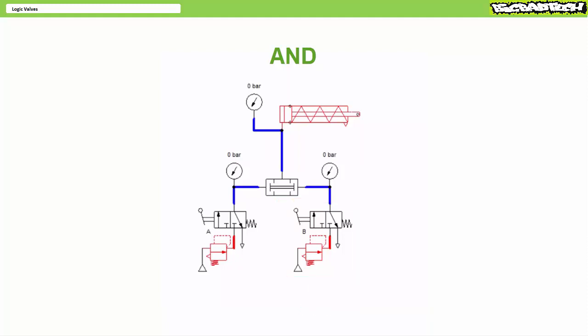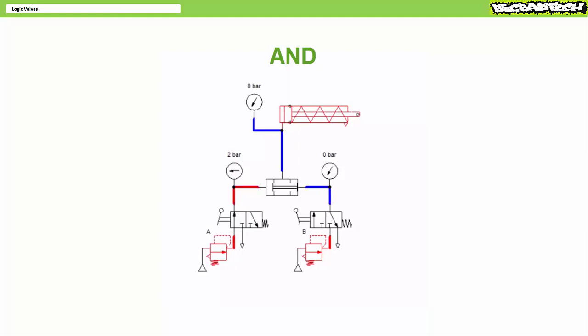Recall an AND valve behaves as follows: there must be a pilot signal at both inputs A and B for there to be an output. Additionally, when both air pilots A and B are present, it selects the lowest of the two pressures. When neither A nor B receive an air pilot signal, the AND valve produces no output. When only A receives a signal, no output. When only B receives a signal, no output. Only when both A and B receive an air pilot signal does the AND valve produce output. You will note the AND valve selects the lowest of the two pressures, notably A at 2 bar.